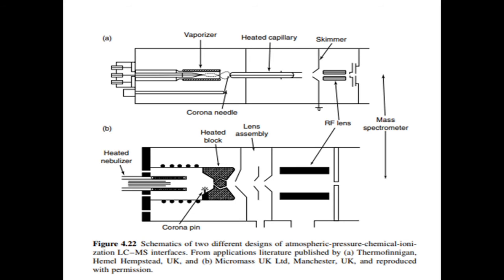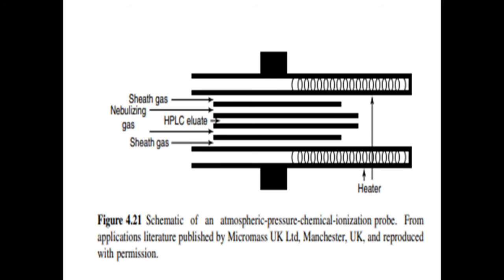The similarity of the hardware required for APCI to that required for electrospray may be seen from comparing figures 4.9 and 4.22, and makes changing between the techniques convenient from a practical point of view. The complementary nature of the two ionization techniques may therefore be readily utilized. Figure 4.21 shows a schematic of an atmospheric pressure chemical ionization probe.